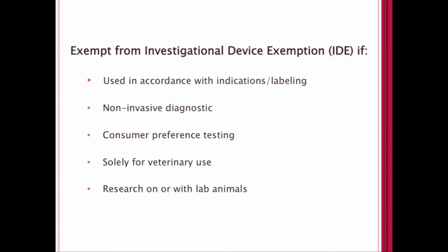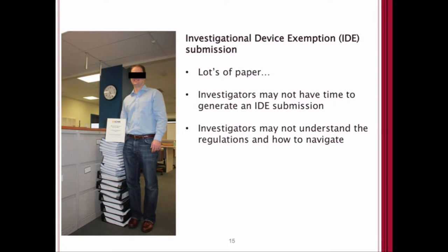You are exempt from IDE regulations if you're using the device in accordance with its indications and labeling, if it's a non-invasive diagnostic, for consumer preference testing, or solely for veterinary use or research on lab animals. An IDE application involves a lot of paper, plus an electronic file of your paper copy. Investigators often don't have the time to generate this IDE submission, and many don't understand the regulations on how to navigate this. For a significant risk device requiring clinical trials, the IDE process can be very time-consuming.